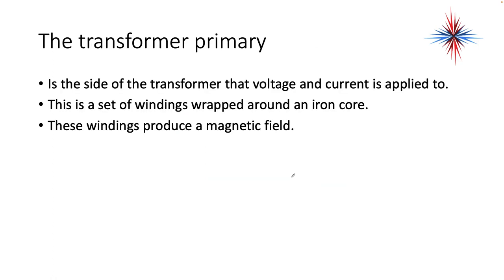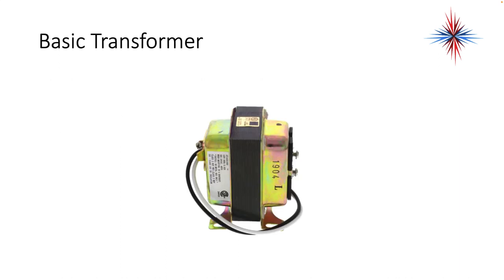The transformer primary is the side of the transformer that voltage and current is applied to. It's a set of windings wrapped around an iron core, and these windings produce a magnetic field. This is a transformer — my primary wiring in this case is the black and white. From experience, when you have a black and a white wire on a transformer, this is going to be a 120-volt primary. And because this is an HVAC transformer, this is going to be labeled 24.